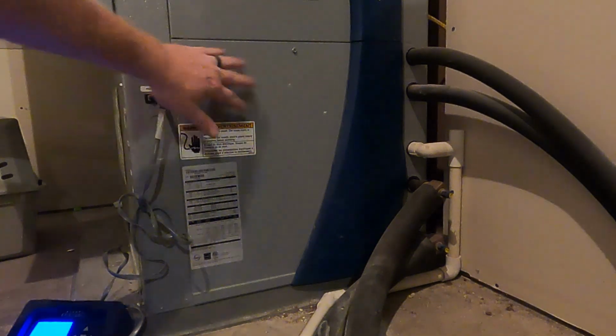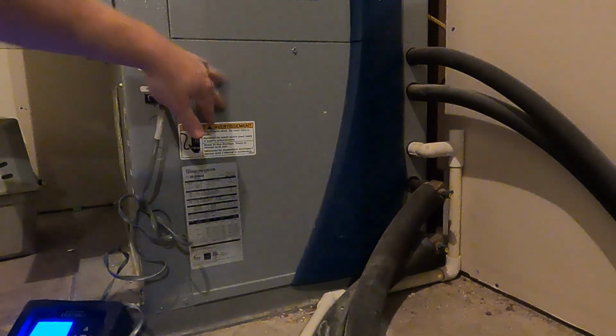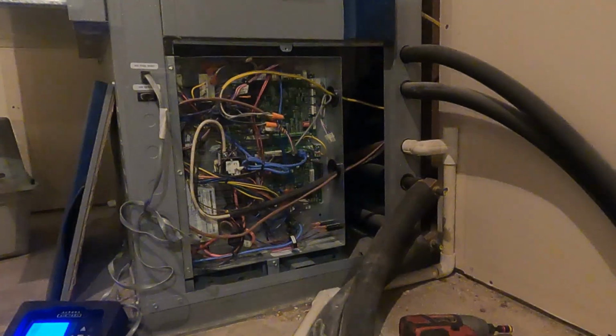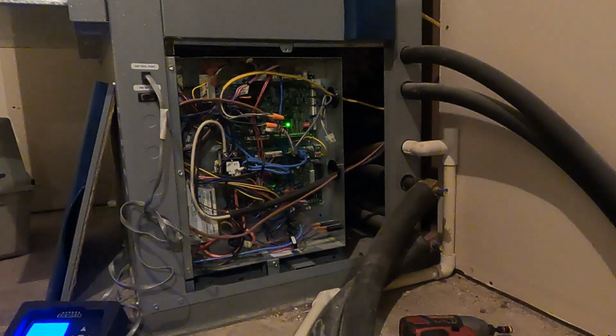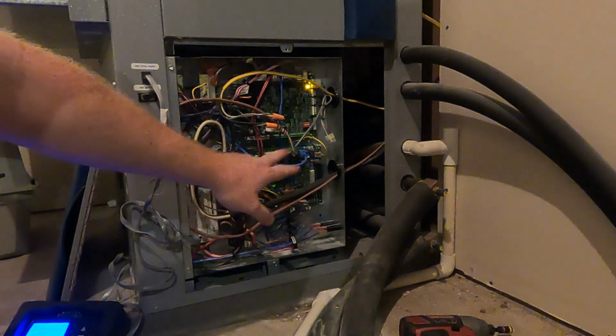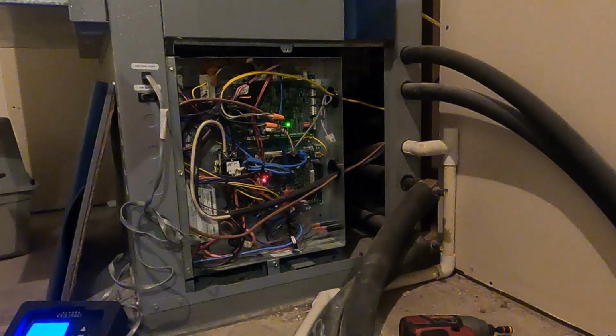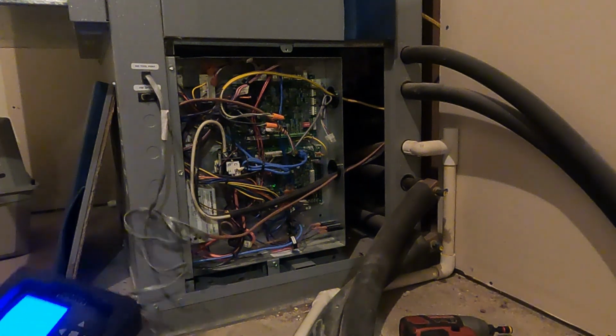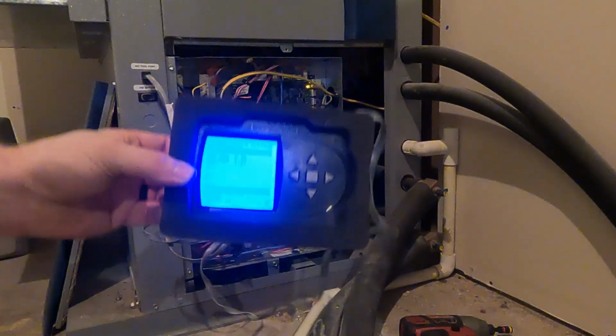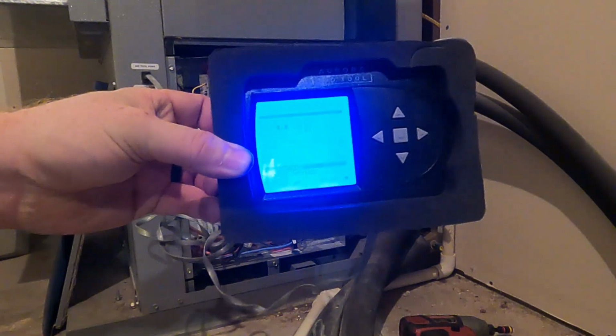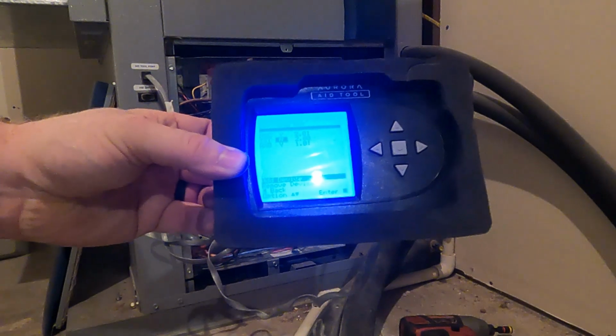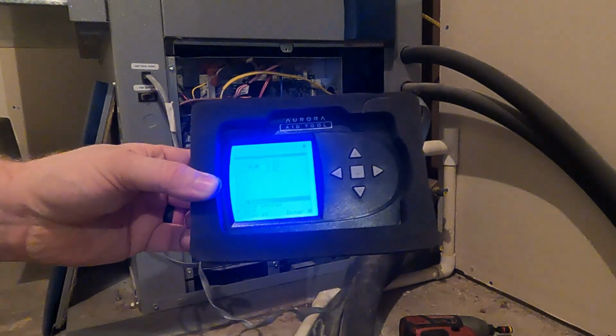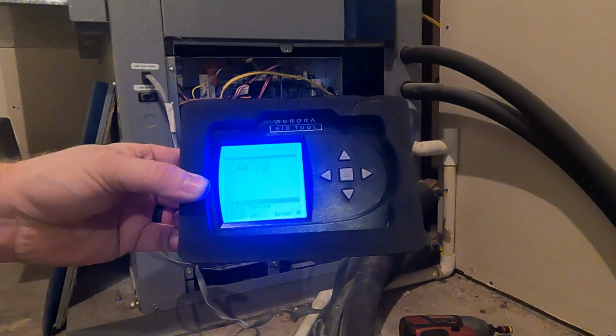Next, we're going to go ahead and open up this bottom door, get to the control panel. Alright, we're into the controls now. Got the same diagnostic blinking light down here showing that same error code. When I pull up the configuration on this, it's showing that it does not sense a thermostat on here. So that's where I'm going to start off at, making sure I'm getting voltage to my thermostat.